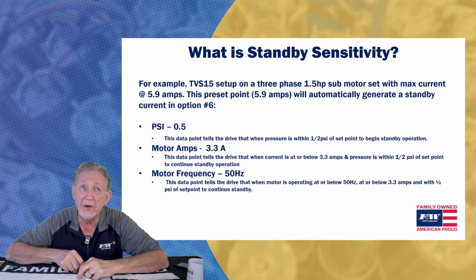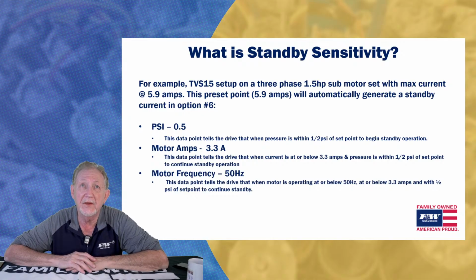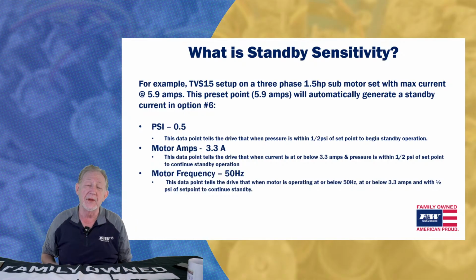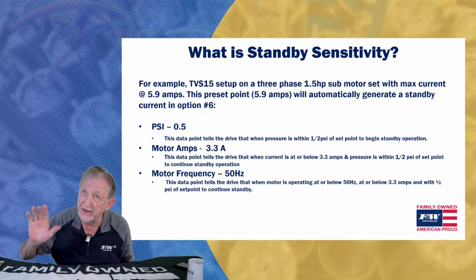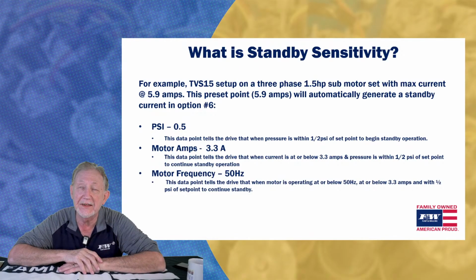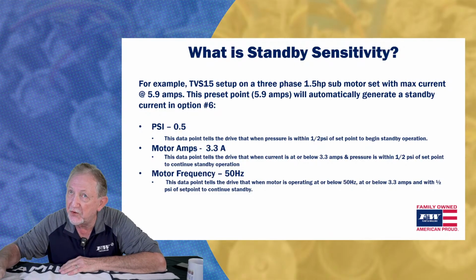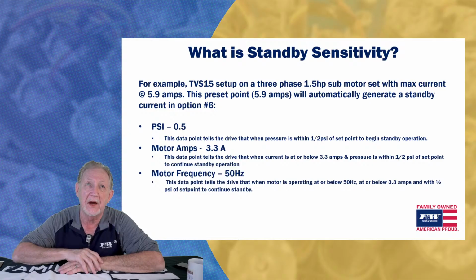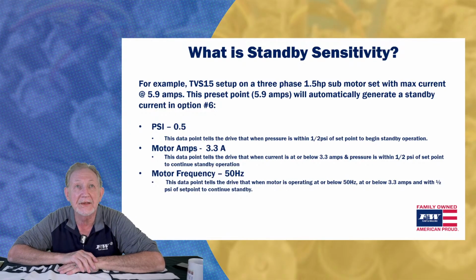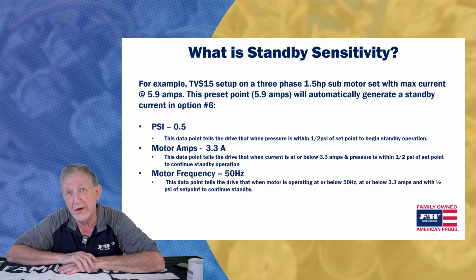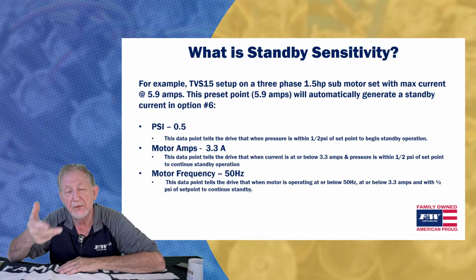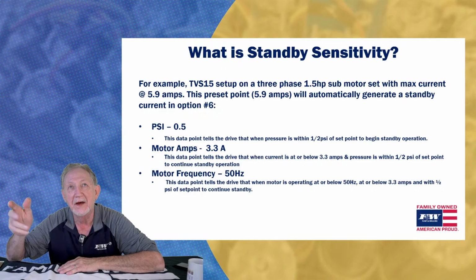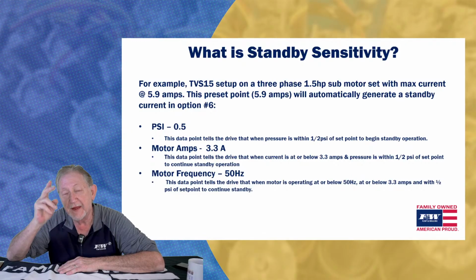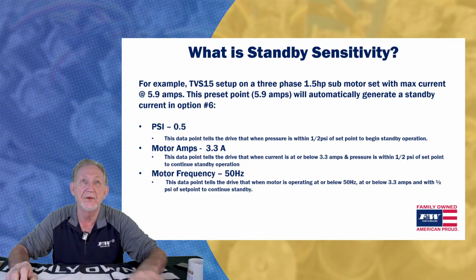So the motor amps. What that data point is going to tell the drive is that when the current is at or below that 3.3 amps and, key word, within a half PSI of that set point, the drive is going to continue down that path of standby. And then the last thing it's going to look at is the motor frequency. So here, if we're running at or below 50 hertz, at or below 3.3 amps, and within a half a pound of the pressure set point, then and only then will that drive go into standby.